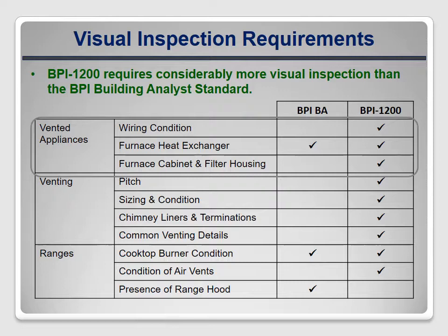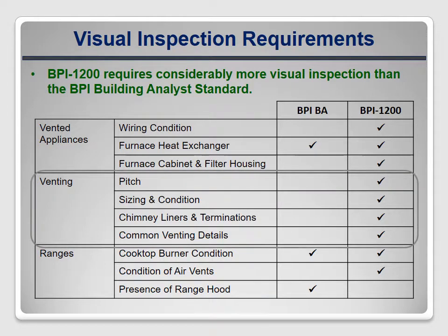BPI 1200 requires a detailed assessment of the venting system, including pitch, supports, sizing, condition, and appropriate handling of common vents shared by multiple appliances. None of this is mentioned in the BA Standard, though as mentioned earlier, it is implied in other BA documents.